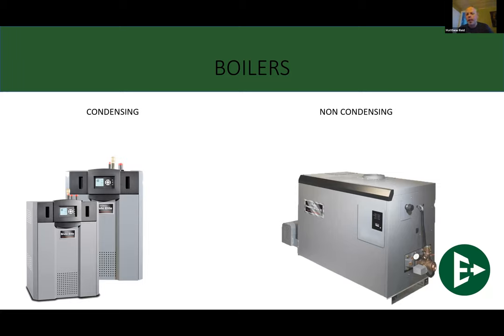Now your non-condensings are designed to work at a much warmer temperature, to see warmer temperatures come back to them on the return. Again, plus 135. I actually like to see plus 140 coming back to non-condensing boilers, 140 minimum, because that heat exchanger is not designed to see condensate. And when I say not designed for it, the condensate that we create with condensing boilers and even non-condensing boilers as it escapes the house, it's mildly acidic.